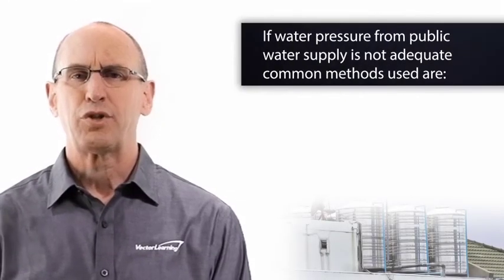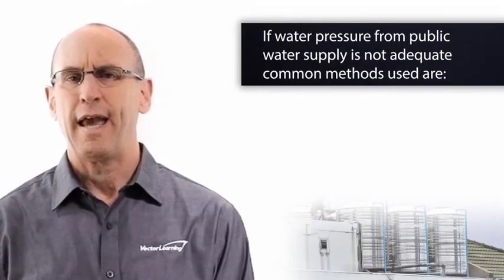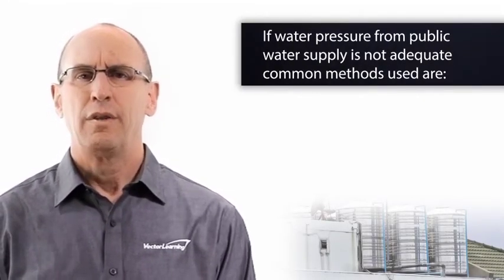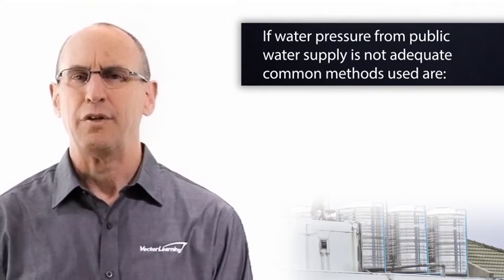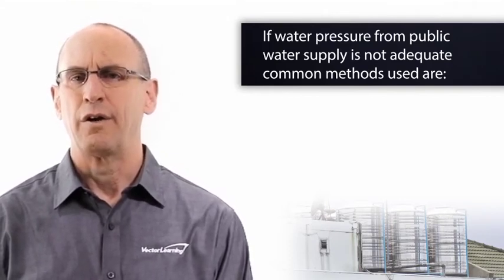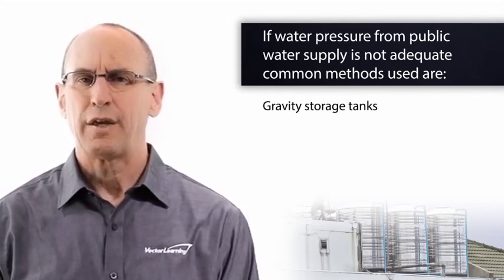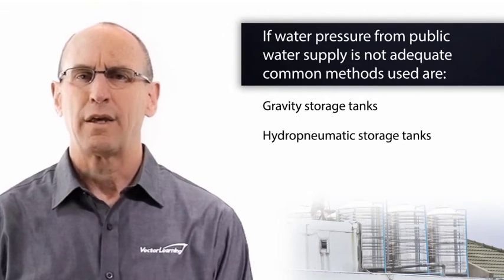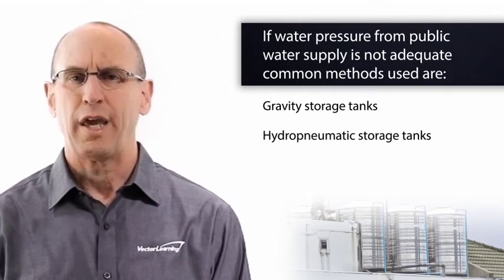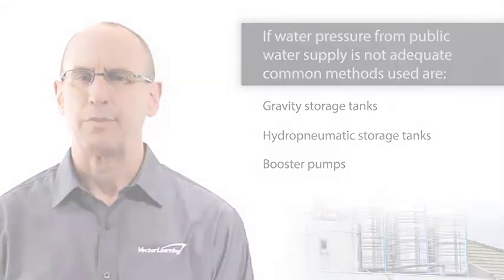If the water pressure from the public water supply is not adequate, the common methods used to handle these conditions are gravity storage tanks, hydropneumatic storage tanks, or booster pumps.